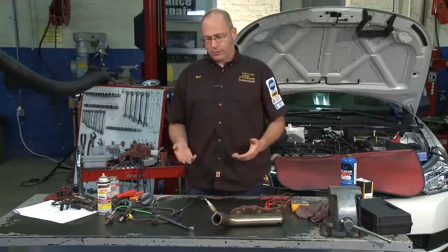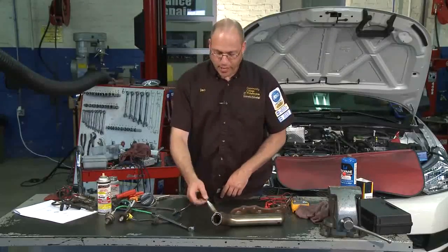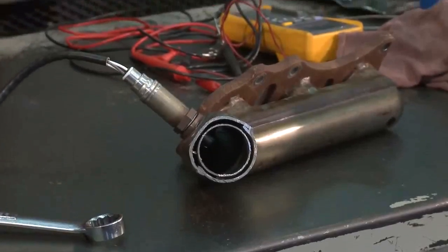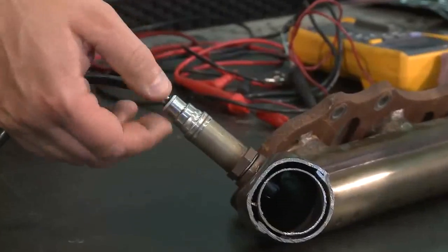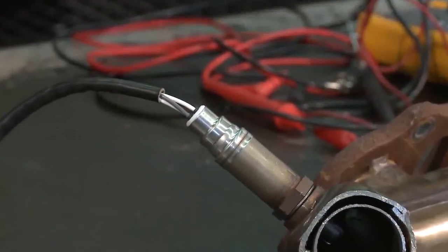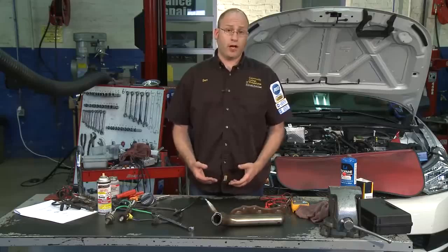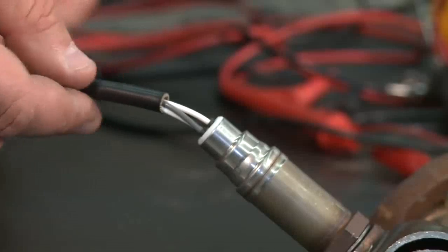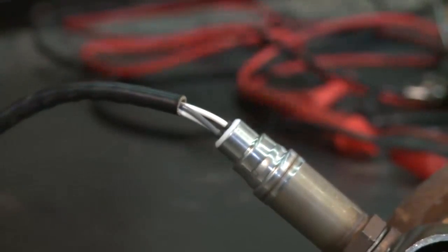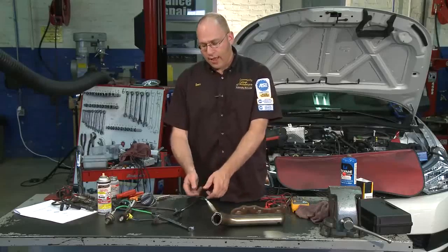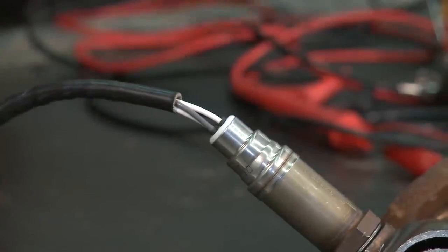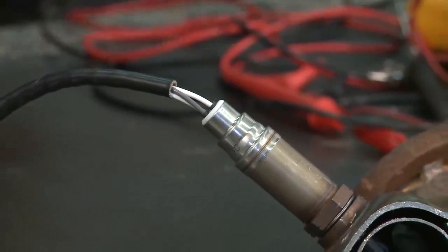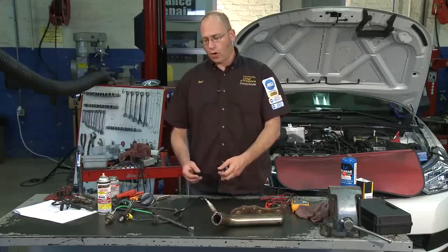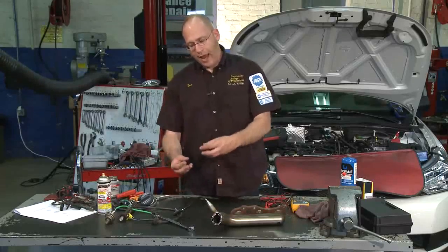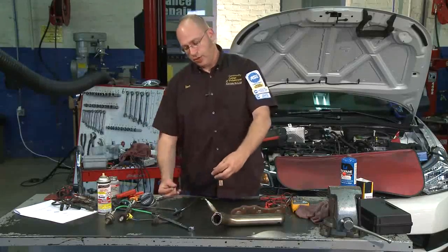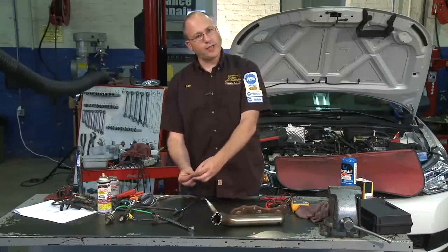The other thing is there's some disagreement from manufacturers about the actual coating of the stainless steel wire covering. This coating has to, again, be able to withstand extreme temperature environments. And if we just put on some electrical tape or some butt connectors or something like that, or even heat shrink tubing, that's going to get really hot and it could actually fail and cause a short or your electrical connections to fall apart.